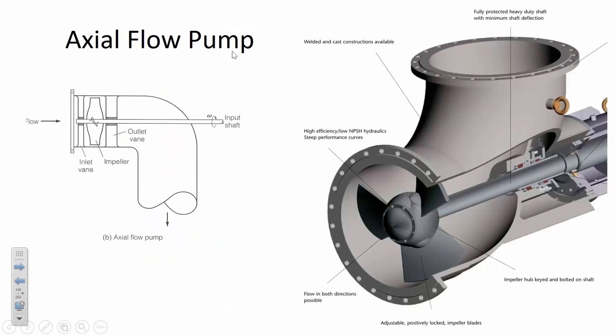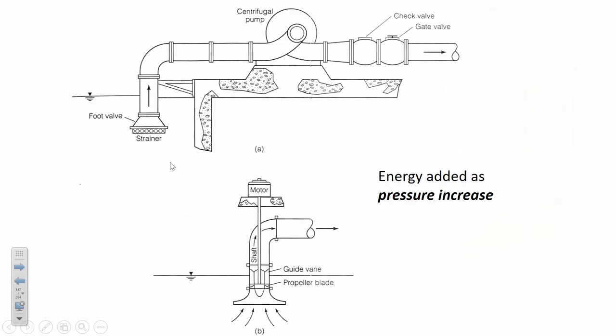An axial flow pump adds energy the same way — an impeller accelerates the fluid and adds pressure — but it allows a really long drive shaft mounted at the surface with the impeller submerged deep underground, potentially hundreds of feet down in an aquifer, while the motor stays at the surface where electricity and cooling are available. Unlike radial flow pumps, axial flow pumps do not change the direction of the flow.